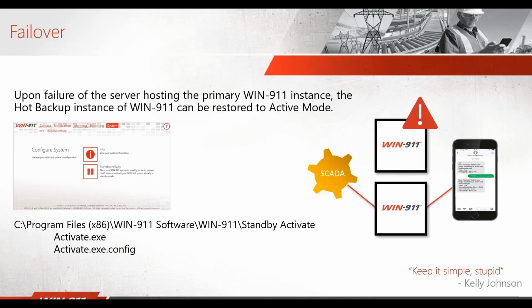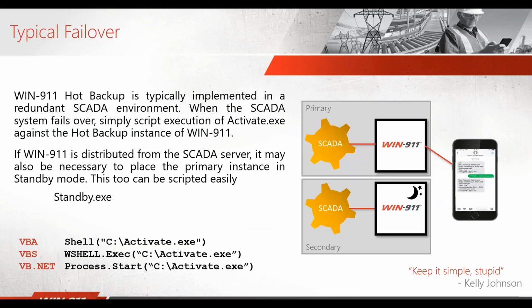So upon a failure, if the primary server failed, you want to activate the secondary server. So you run this activate executable. It's configured to activate the secondary system. And now that system, which was also receiving alarms, so they were in sync as far as alarms go, takes over notification and starts sending out notifications to your operators. So that's a typical failover scenario.